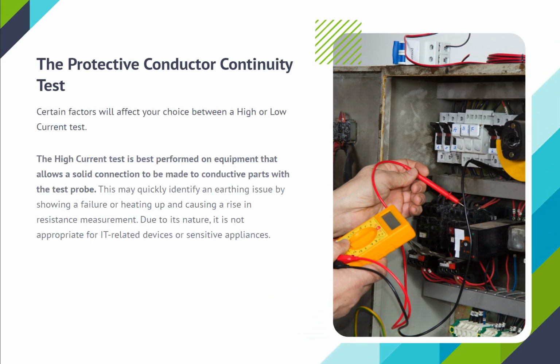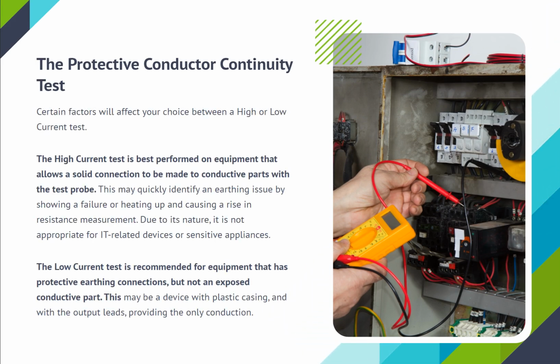Certain factors will affect your choice between a high or low current test. The high current test is best performed on equipment that allows a solid connection to be made to conductive parts with the test probe. This may quickly identify an earthing issue by showing a failure, or heating up and causing a rise in resistance measurement. Due to its nature, it is not appropriate for IT-related devices or sensitive appliances. The low current test is recommended for equipment that has protective earthing connections, but not an exposed conductive part. This may be a device with plastic casing and with the output leads providing the only conduction.